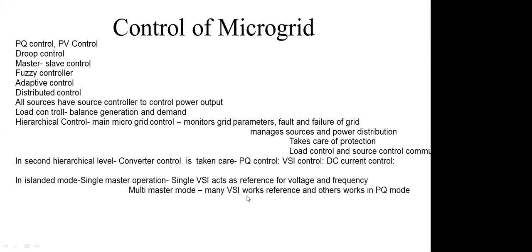In islanding mode, you can have single master or multiple master. In single master, a single inverter gives all the reference voltage and frequency. In multi-master mode, you have many VSIs which give the reference, and apart from those VSIs, the other inverters work in PQ mode.